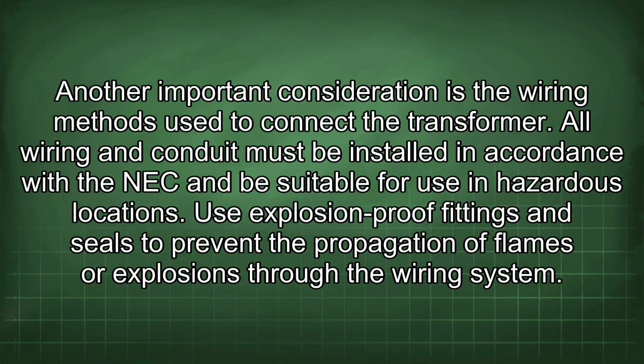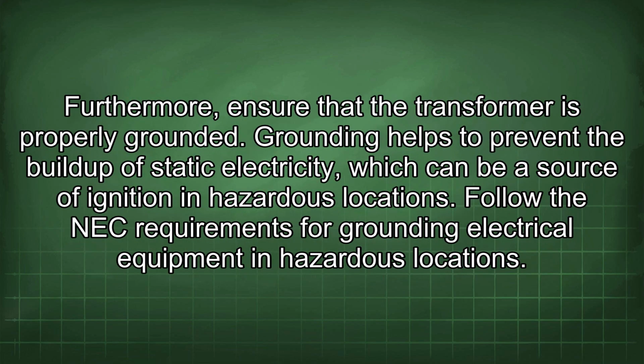Another important consideration is the wiring methods used to connect the transformer. All wiring and conduit must be installed in accordance with the NEC and be suitable for use in hazardous locations. Use explosion-proof fittings and seals to prevent the propagation of flames or explosions through the wiring system. Furthermore, ensure that the transformer is properly grounded. Grounding helps to prevent the buildup of static electricity, which can be a source of ignition in hazardous locations. Follow the NEC requirements for grounding electrical equipment in hazardous locations.